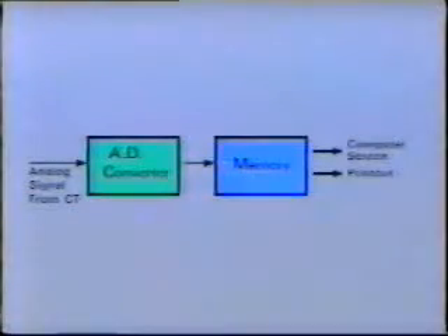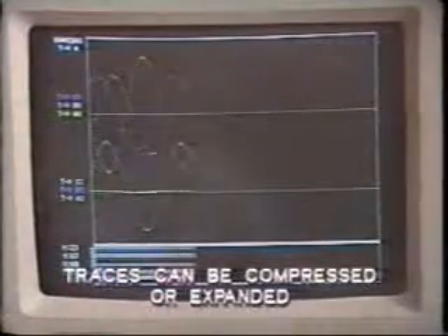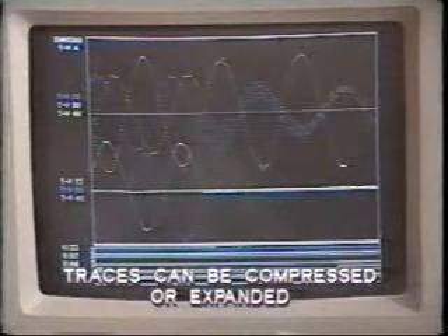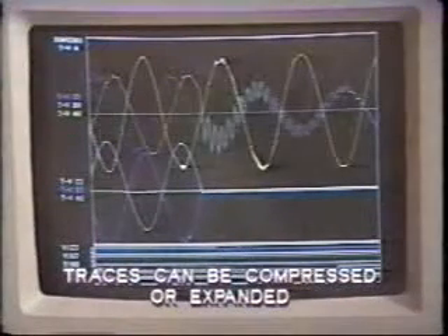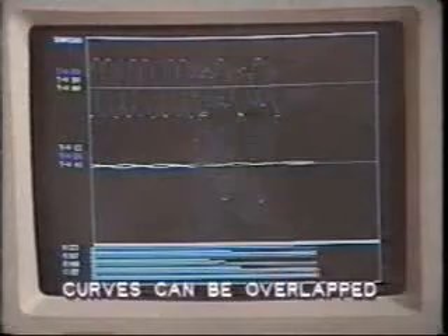This type of system usually allows for a greater number of monitoring inputs. The measurement, that is, sampling, is made simultaneously from all inputs, and a very high rate of sampling is achieved, say 6,000 measurements per second. The analog input is converted through an AD converter into a digital signal to be recorded in the memory of the recorder. The information can be viewed on the computer screen or printed out as required. Usually, the screen traces can be compressed or expanded in both time and amplitude so that a variety of signals can be compared. For precise examination, the curves can be overlapped.